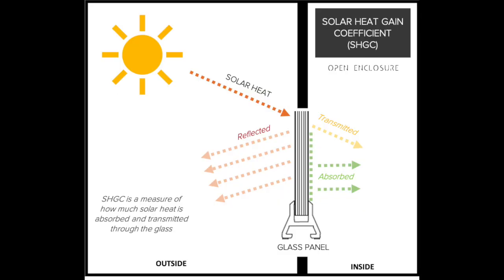Solar heat gain coefficient is the fraction of solar radiation admitted through a window, door, or skylight, either transmitted directly or absorbed and subsequently released as heat inside a building. The lower the SHGC, the less solar heat it transmits and the greater its shading ability. A product with a high SHGC rating is more effective at collecting solar heat during the winter. A product with a low SHGC rating is more effective at reducing cooling loads during the summer by blocking heat gain from the sun.